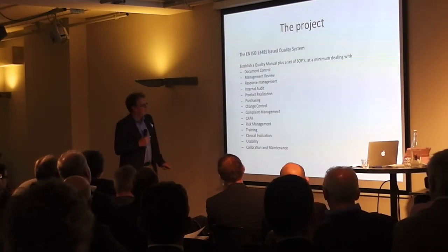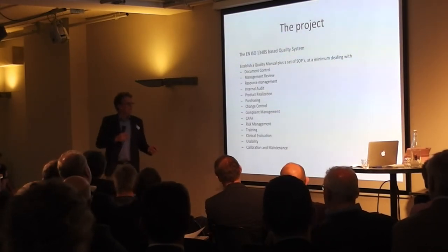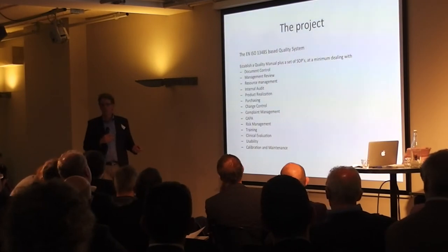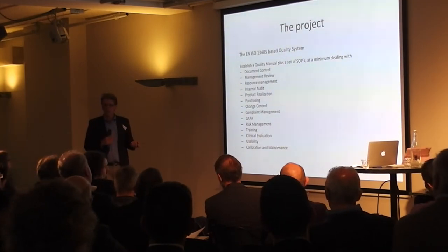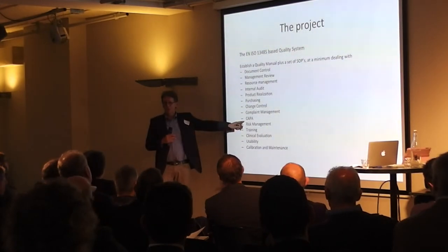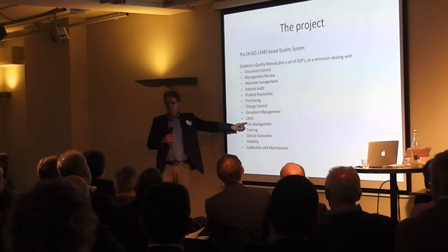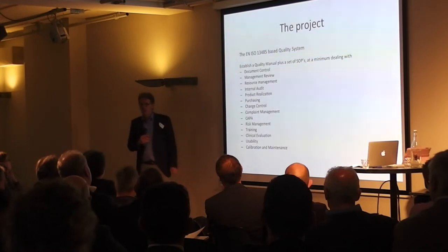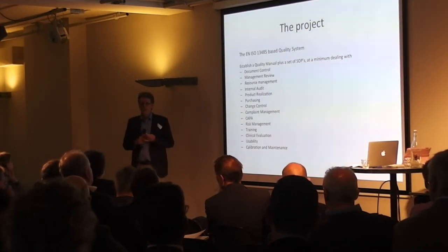Oh, sorry. CAPA is: the moment you encounter a complaint or something which is not working the way it should, you should do a corrective action and solve the issue. But if there is something fundamentally wrong or that needs to be changed on a systematic level, then you also need a preventive action, so adapt your quality system to prevent the reoccurrence.